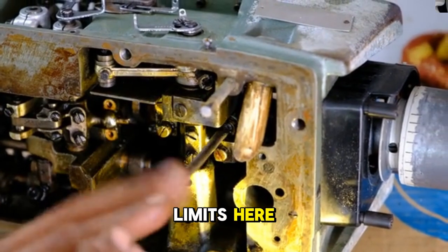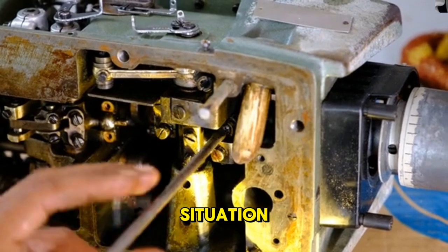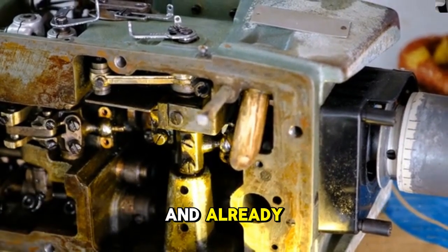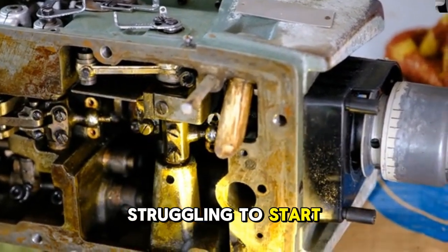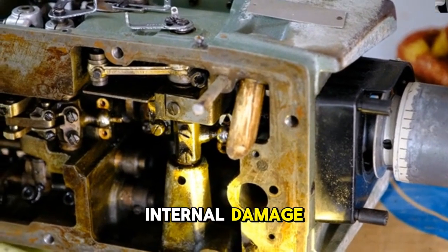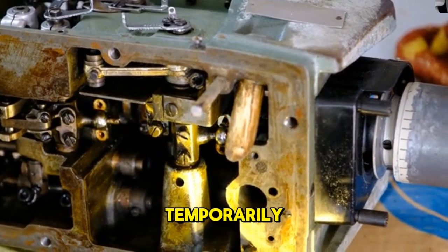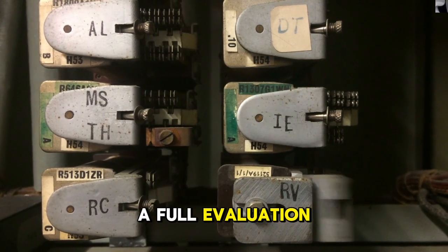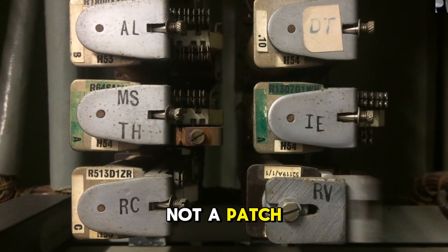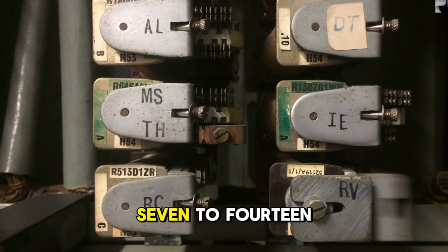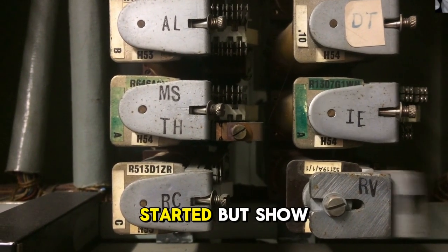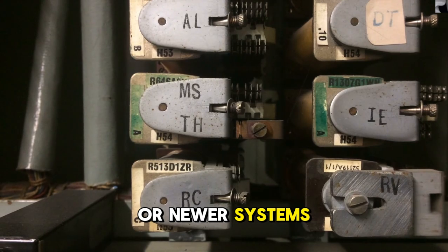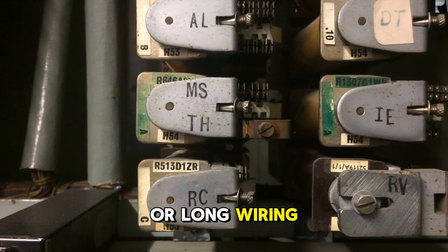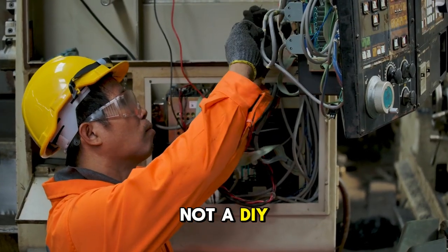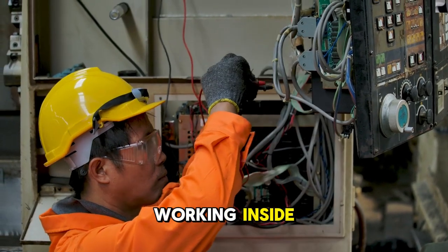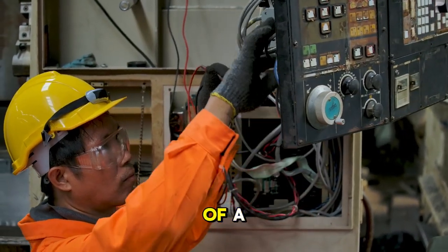A word of honesty on the limits here: this isn't a fix for every situation. If your system is more than 15 years old and already failing internally rather than just struggling to start, a hard start kit won't undo real internal damage. It just gets a dying compressor moving temporarily. In that case, a full evaluation is the more honest path, not a patch. Where it genuinely shines is on systems roughly 7 to 14 years old that run fine once started, but show startup symptoms, or newer systems in homes with weaker incoming voltage or long wiring runs to the outdoor unit. And this is not a DIY electrical project. It involves working inside a high voltage panel, and it belongs in the hands of a licensed technician.